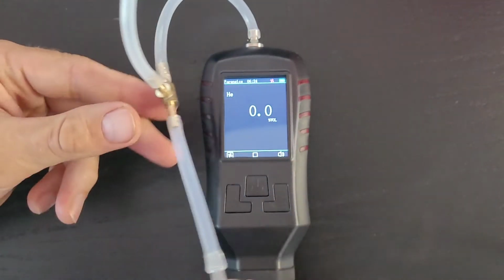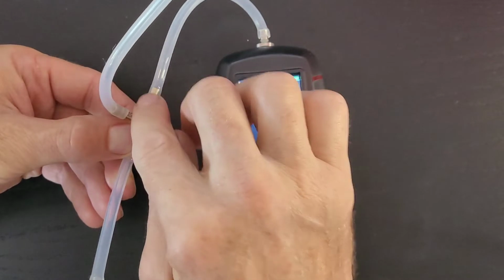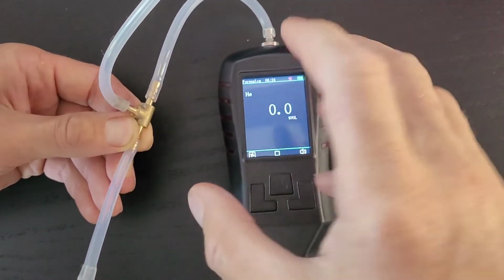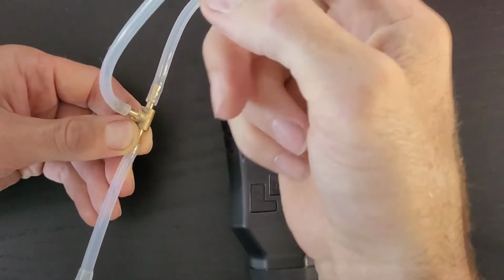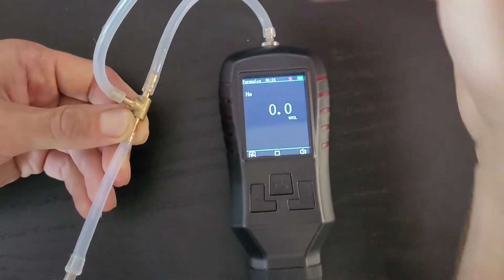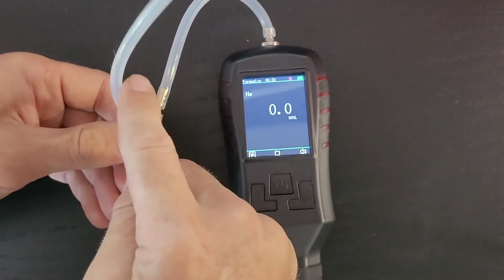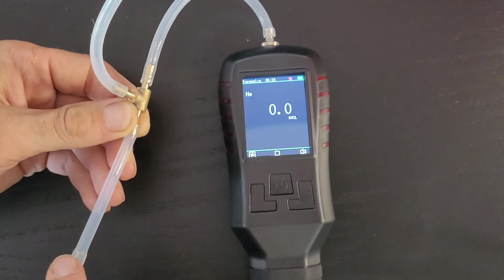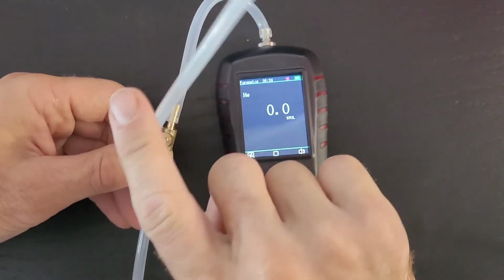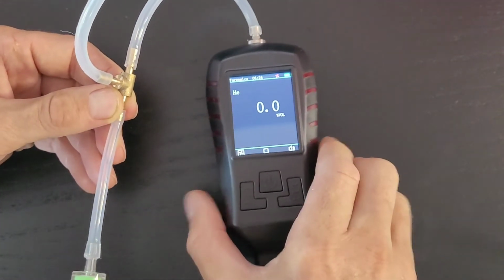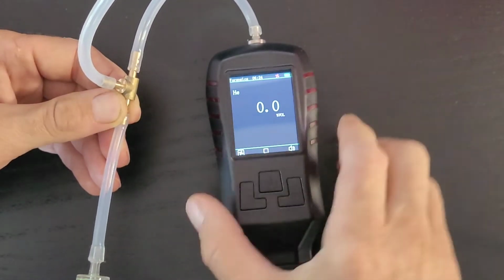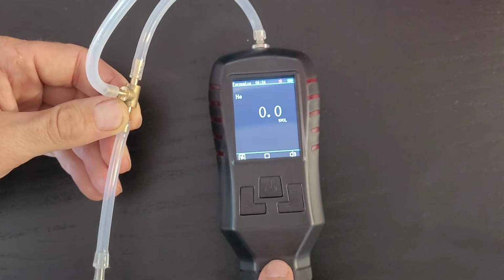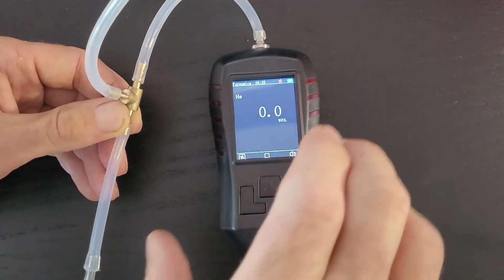Now, why is a T-piece needed? Well, it's because this has a pump, and the T-piece regulates or gives the pump an access point for extra air if needed, if this is restricted, or if there's too much air, the source can exhaust from this outlet, okay, folks? And that ensures the micro pump always has a constant flow, no matter what the source line pressure or flow is at. Okay, folks, it's very important to ensure good, accurate calibration, especially with analyzers with a micro pump. Because I know there's all these other ways of doing it with demand flow regulators and things like that, but I like doing it the old school way, folks. And this ensures we're not stressing or limiting the pump.